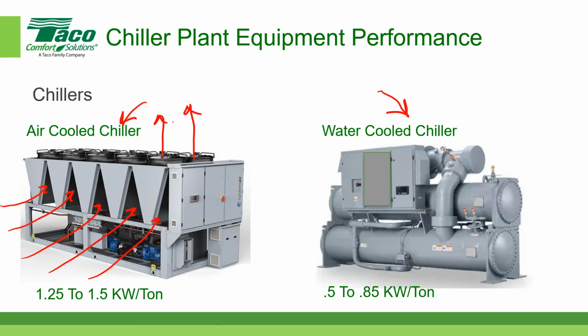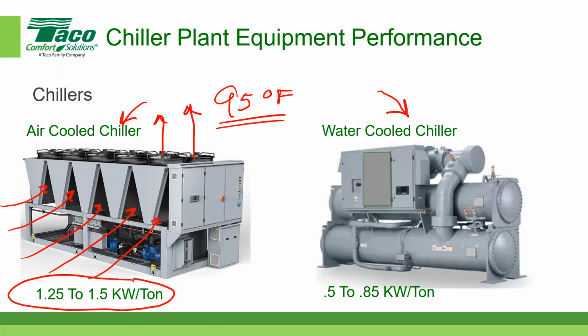And let's say that the ambient temperature is somewhere around 95. It could be higher, but we're just going to pick 95 for the fun of it. If the ambient temperature is 95 degrees, that means the condenser itself has to be at a higher temperature in order for the heat transfer to take place. So basically, we're rejecting heat at an ambient temperature of about 95 degrees Fahrenheit. And the amount of power that an air-cooled chiller typically consumes is somewhere between 1.25 and 1.5 kW per ton.